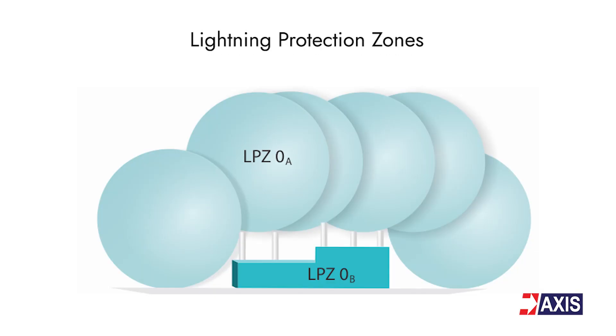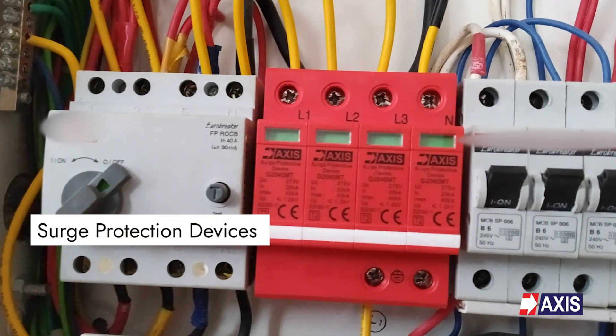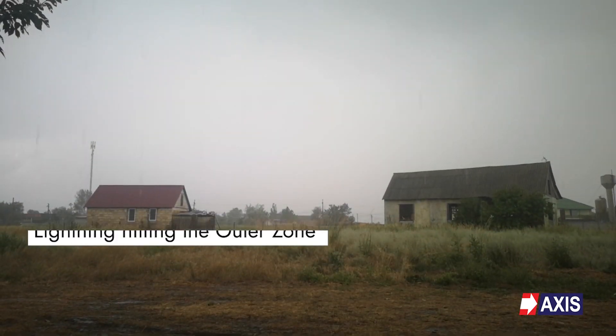Part 4 also introduces lightning protection zones. The central idea is to limit current and voltage surges by dividing the structure into different risk zones. These zones are nested within each other, with the most sensitive zones being the innermost. An assessment is performed for each zone to select the most appropriate protection at the optimum cost. By using standard appropriate solutions like lightning arrestors and surge protection devices, the effects of lightning hitting the outer zone are meant to be reduced before they can affect people or sensitive equipment in the inner zones.